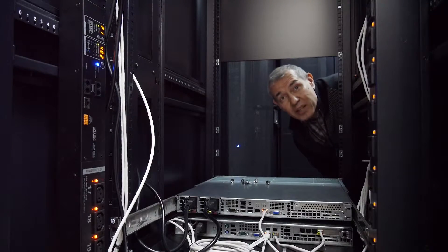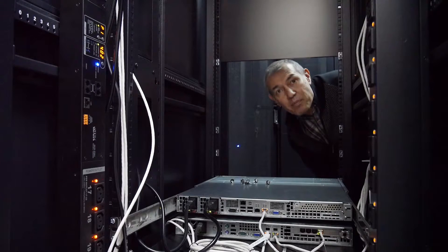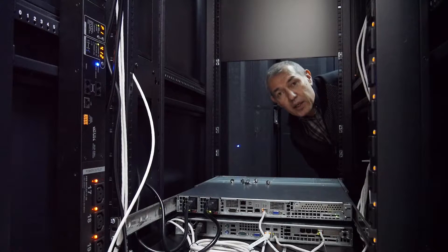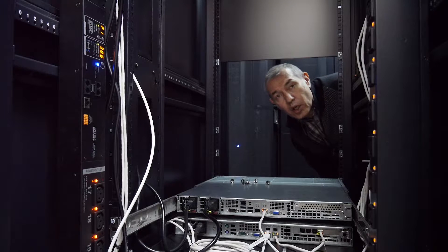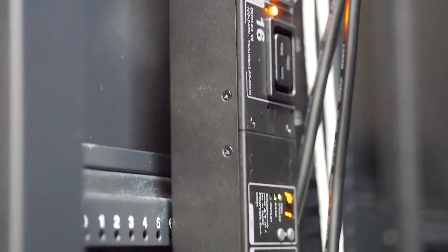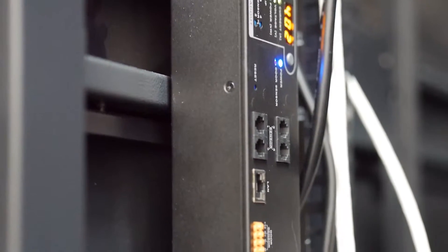Each server rack in my data center has two IPPDUs. Each IPPDU is 32 ampere and has 32 controllable power outlets of different types. Each IPPDU also has sensors to measure temperature and humidity inside and outside of the server rack. It is very important that each IPPDU has an RJ45 connector and a browser which allows customers to control power parameters in each unit.